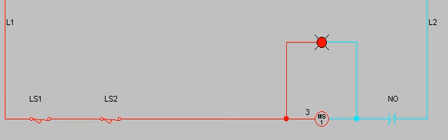Okay, so hopefully, as we see now, with both switches closed, current flows through, and in this condition we have a normally open contact. I'm going to go ahead and try on this simulation to say, what if we did have an overload here? We see that we would get the same thing. We would turn off the circuit, interrupting current flow because we have an overload condition in the motor.